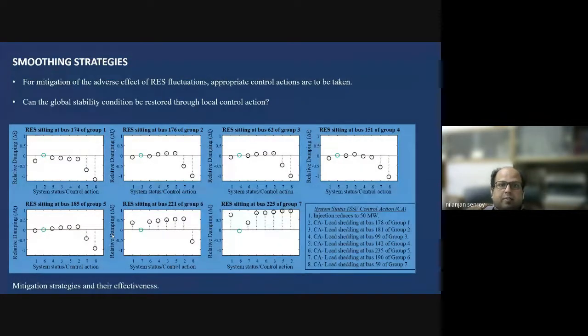So once you have identified these groups, we have come up with a control strategy: if you are having fluctuations in renewable energy injection, then these fluctuations may be compensated by appropriate action from an energy storage device. So for instance, if you have a 100 megawatt wind farm, which is currently generating 75 megawatts, then this 75 megawatts may suddenly drop to 72 megawatts. The 3 megawatt fluctuation that has happened may be compensated by an additional 3 megawatt generation from the energy storage that is there. The question is where to locate the energy storage device.